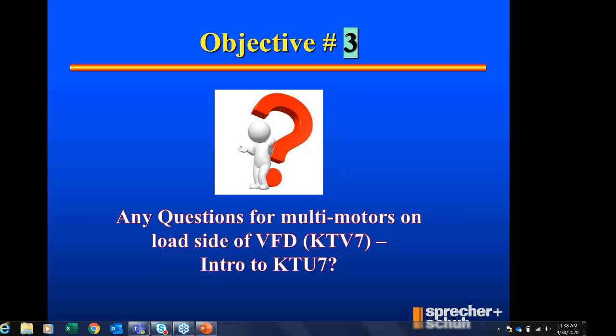Next question is, can you bypass the VFD if necessary? I think that is more of a circuit question than a product capability question, so I'll kind of bypass that question. Yeah, and the answer is yes, they can. Obviously with contactors, you can do a three contactor bypass isolation. So the next question is, please give examples of an application with one VFD and multiple motors. Why not use one VFD per motor?